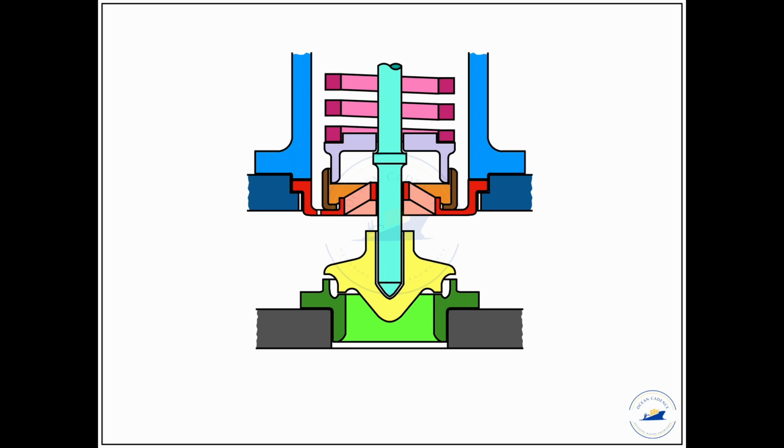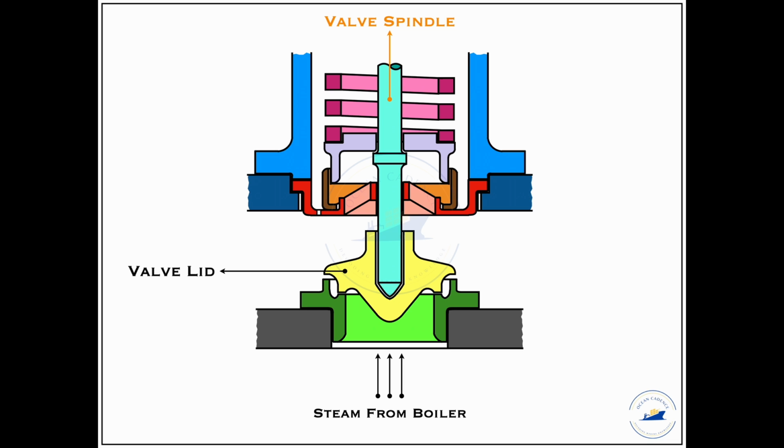As we can see, the steam directly acts on the lower end of the valve lid, thereby giving it the initial lift, and then goes on to the additional channels from where it gives the additional lift, and the spindle along with the valve lid completely lifts off the valve seat.